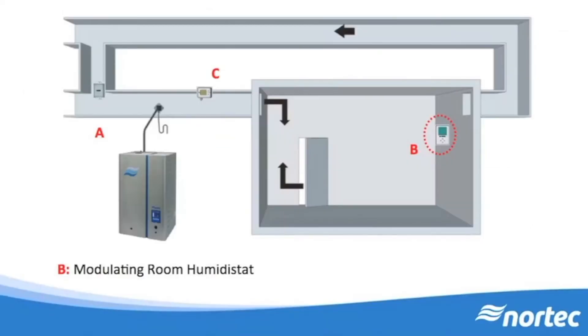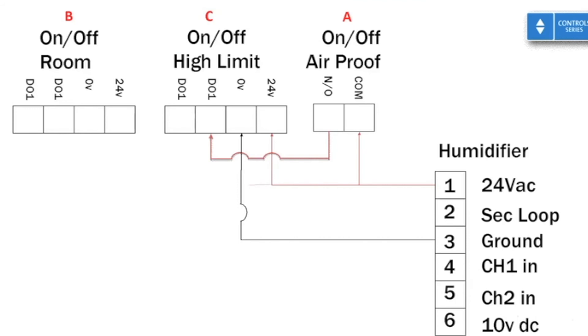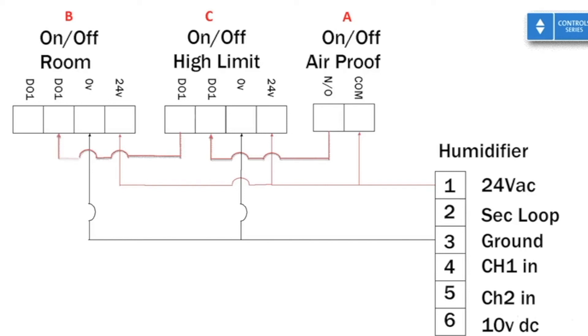The on-off room humidistat requires power and ground from the humidifier. We tap off the same 24 volt AC supply as the previous high limit and wire to the respective terminals on the humidistat, doing the same with the ground. The conductor from the on-off high limit is used as the incoming signal to this humidistat's relay. As long as both the air proving switch and the high limit complete the loop, the signal can be relayed to the humidifier security loop should there be a need for humidification. The relay output goes to the humidifier security loop, pin 2.